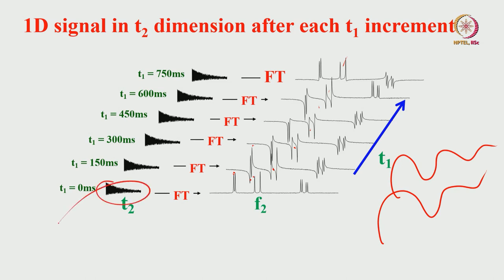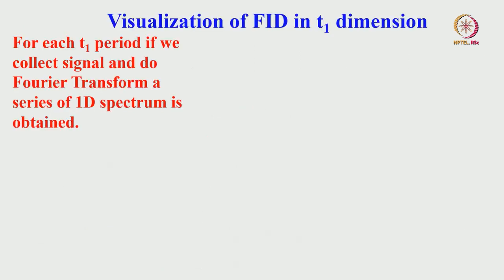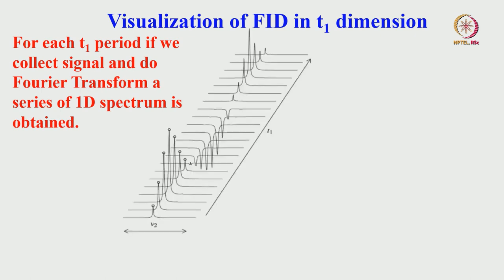This oscillatory behavior forms what is called an interferogram — a time-domain signal in the T1 dimension, similar to what we saw in the T2 period. Typically, about 100 to 512 T1 points are collected. For each T1 period, if you collect the signal and do Fourier transformation, you get a series of 1D spectra — one for each T1 point. The intensity of each peak in these spectra is oscillating as a function of T1.